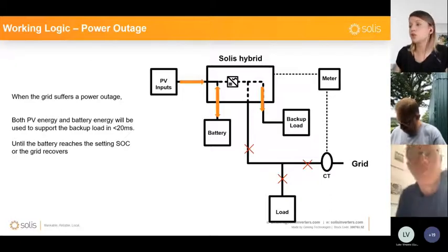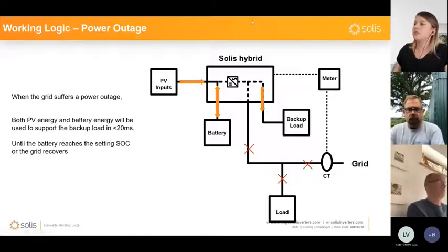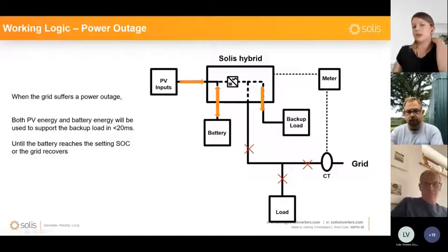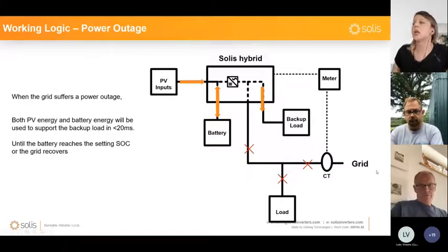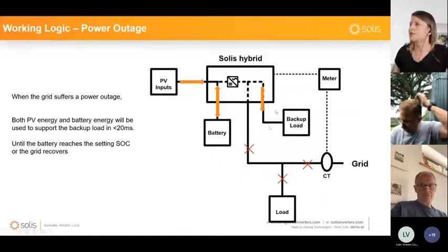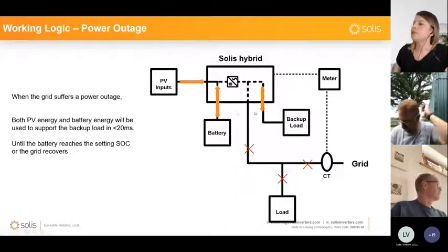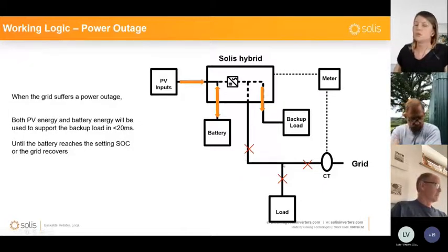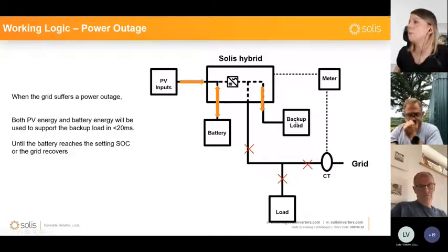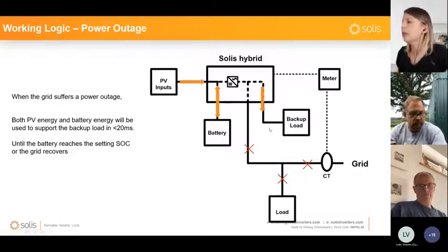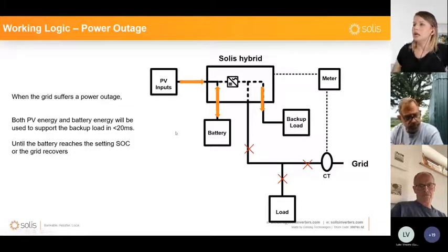an external switch. But what we advise, and I'll tell you a bit later, I have a diagram, is that there should be a changeover switch just for maintenance purposes. So in case you have the hybrid taken out of service for some reason, there should be a changeover switch to switch the supply for these backup loads to the grid. It can be manual, it can be automatic, depending on what the customer wants or needs. But yeah, it does need to be there.